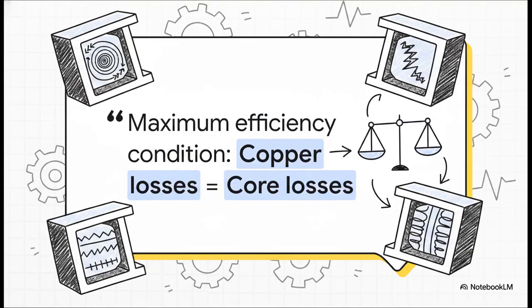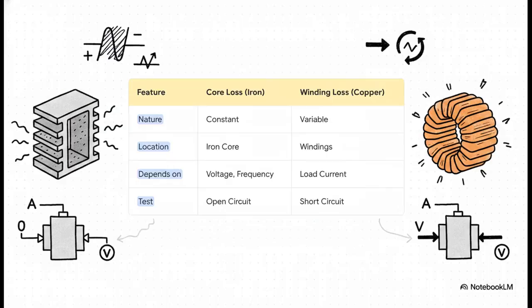And all of this leads to this really beautiful, elegant principle in transformer design. A transformer is running at its absolute most efficient when the constant core losses are perfectly balanced by the variable copper losses. It's this perfect sweet spot where the total combined losses are as low as they can be and the transformer is just humming along at peak performance. So let's just recap our whole investigation with this table. You can see it all laid out here. Core loss on the left is constant, and it happens in the iron core. Winding loss on the right is variable and happens in the copper windings. And notice this. Core loss depends on voltage, but the winding loss depends entirely on the current being drawn. Engineers even have specific tests, like the open circuit test and short circuit test, to measure each of these precisely.